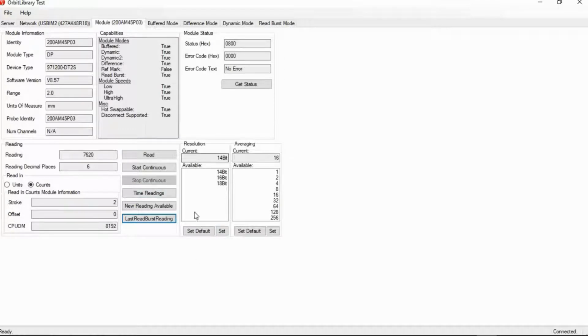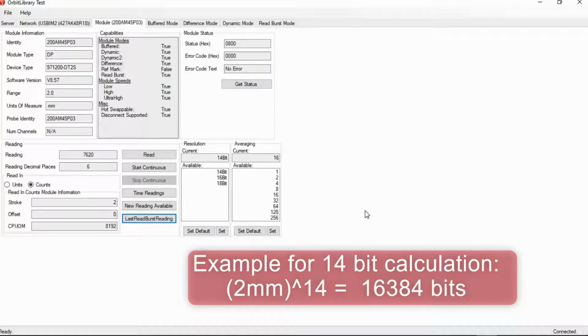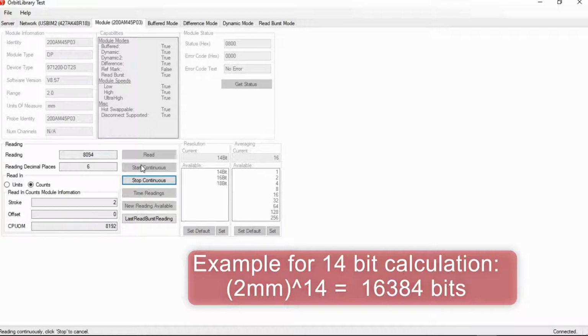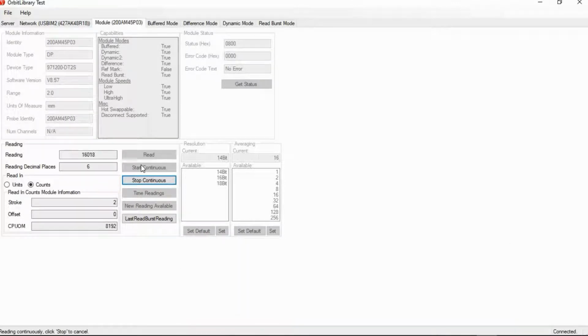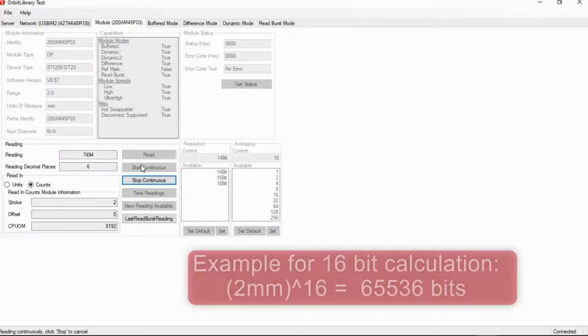Now that leads to the next display over here, resolution. Basically, notice how it's listed in 14-bit, 16-bit, or 18-bit. That has to do with the number of bits to define how high a resolution you can go. And when it says 14-bit, what that actually means is 2 to the 14 bits, which would be 16,384 bits. Now if I click Start Continuous again, and then move the probe tip all the way to the end of its range, what's it going to finish at? About 16,384 bits. Now those are about the number of many times the reading can change across the measurement range.